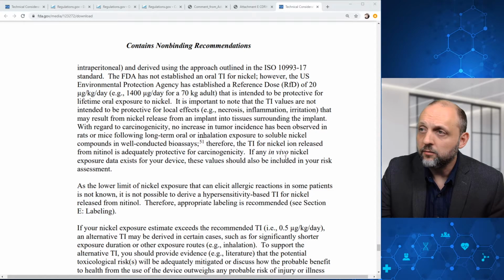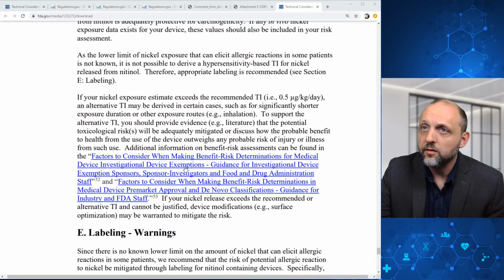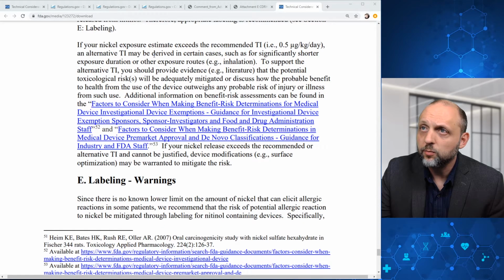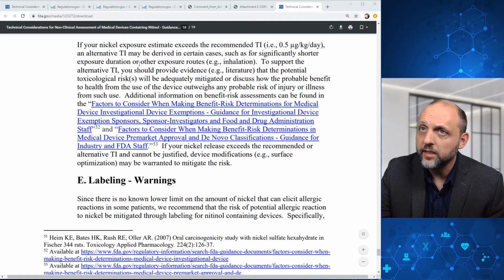And if any in vivo nickel exposure data exists for your device, these values should also be included in your risk assessment. As the lower limit of nickel exposure that can elicit allergic reactions in some patients is not known, it's not possible to derive a hypersensitivity based tolerable intake for nickel released from nitinol. Therefore, appropriate labeling is recommended. And if your nickel exposure estimate exceeds the recommended tolerable intake, an alternative tolerable intake may be derived in certain cases. And here, FDA provides some additional links.